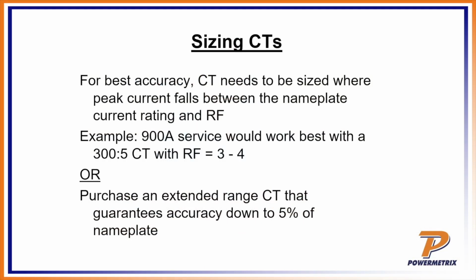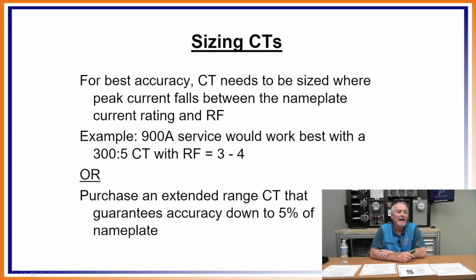Sizing CTs. Okay, so for best accuracy, a CT needs to be sized where the peak current falls between the nameplate current rating and the rating factor. Because one of the cool things about this rating factor is, remember we talked about the bathtub curve, where as long as you were at 100% rating of that CT, the accuracy was 0.3. As soon as I got less than that, it was 0.6. It doubled the inaccuracy. It was twice as less accurate, from 0.3 to 0.6.